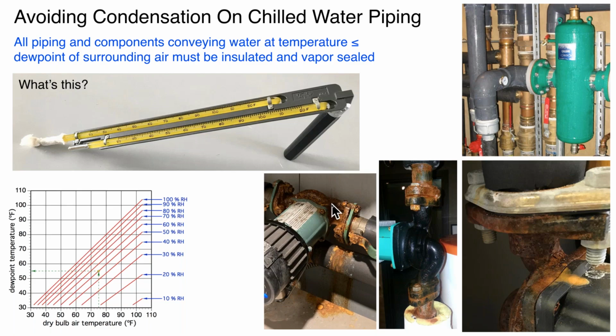We don't run that cooling except from May to October. It might be just 2 months of cooling. You can see the piping next to the pump or the circulator is insulated, but you can see the surface oxidation, not only on the pump volute, but also on the steel hardware on the isolation flanges here. This is zinc plated hardware that's also corroded, and you can see where the condensate has dripped and eventually dripped down on top of something else in the system.